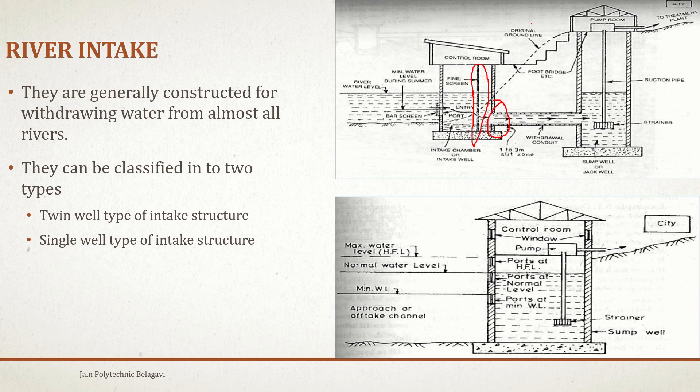This is about the twin well type intake structure. For the single well type of intake structure, there are three inlet pipes: the first at high flood level, the second at normal water level, and the third at minimum water level. Below the minimum water level, no water is available as it drains off.